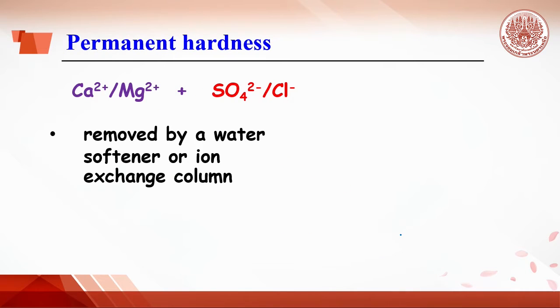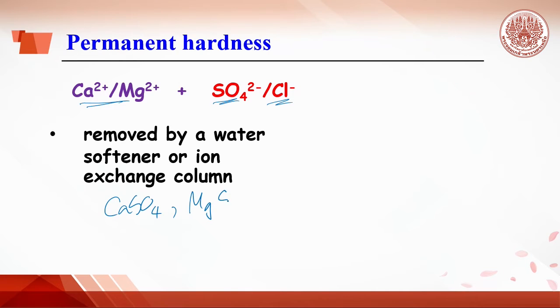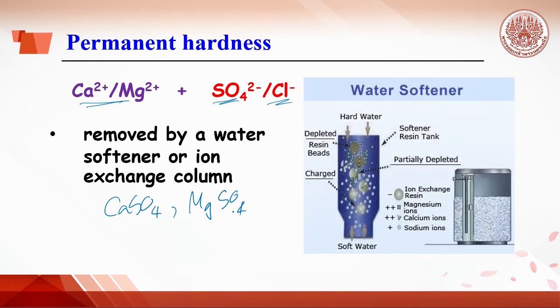Permanent hardness is caused by the presence of calcium ions together with non-carbonate anions such as sulfate or chloride ions. Calcium sulfate or magnesium sulfate do not precipitate out as temperature increases, so permanent hardness cannot be removed by boiling. It can be removed using a water softener or ion exchange column.